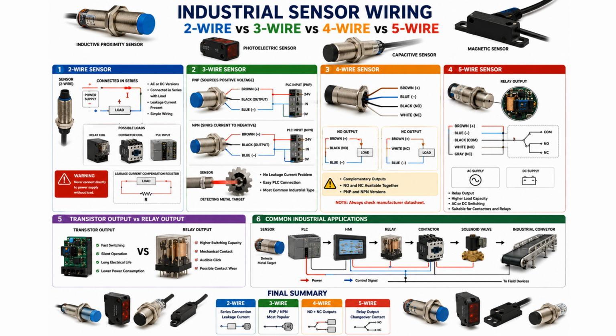Final comparison. If we want to summarize everything in a very simple way. 2-wire sensors. The simplest type. 3-wire sensors. The most widely used type in industry. 4-wire sensors. Provide both NO and NC output simultaneously. 5-wire sensors. Typically feature a relay output and are suitable for a wide variety of loads.